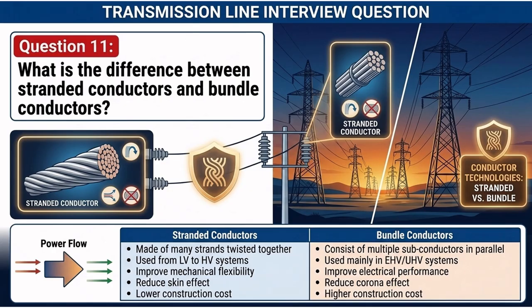What is the difference between stranded conductors and bundle conductors? Stranded conductors are made of many twisted strands, providing excellent mechanical flexibility, and are widely used from low to high voltage systems. Bundle conductors, however, consist of two or more parallel subconductors and are mainly used in extra high voltage transmission lines to reduce corona loss and improve electrical performance, although they are more expensive.